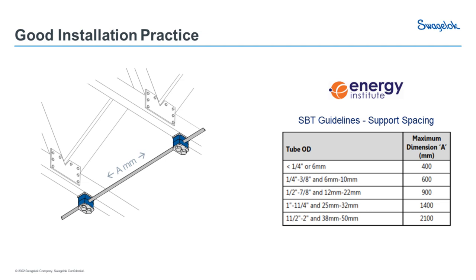The Energy Institute has a very good standard that this table comes from — it talks about the spacing between tube supports. Depending on the diameter of the tube, you should put your tube supports in every X distance. This is also in the Swagelok Tube Fitters Manual — the big blue book you get on one of our training courses. The guidelines are called 'Guidelines for the Design, Installation and Management of Small Bore Tubing Assemblies.' Lots of information in this about vibration, dynamic movement, spacing — and it's manufacturer-agnostic, so there's lots of general industry detail.